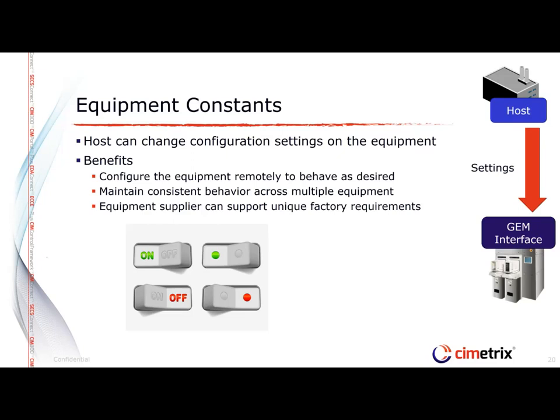GEM also allows for equipment constants — this is how you configure equipment behavior remotely, and it's particularly useful if there are a number of pieces of equipment at the factory and you want consistent behavior across all of them. Typical equipment constants on a GEM interface are things like options — for example, when a board comes in, you may have an option to have the operator stop, inspect, and confirm that it's the right board or the right lot.